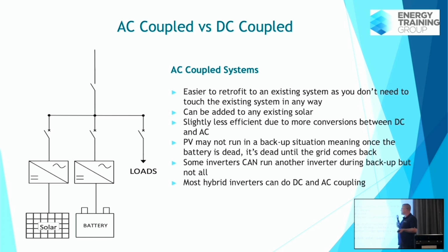It's obviously slightly less efficient than DC coupled because you've got a few more conversions. In terms of backup, not all AC coupled systems, when in off-grid mode, will be able to start the other inverter - some technologies can and some can't. So it's really important you understand what you're selling, and whether your battery, in backup mode, can actually start a third-party inverter or not. Different inverters are different and the list is very long, so I'm not going into it, but you need to make sure you're researching that.